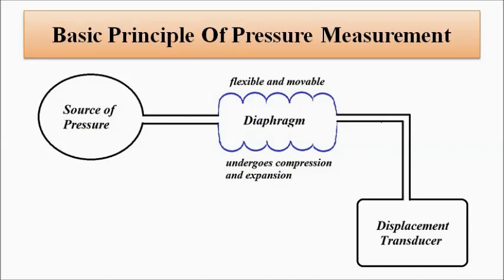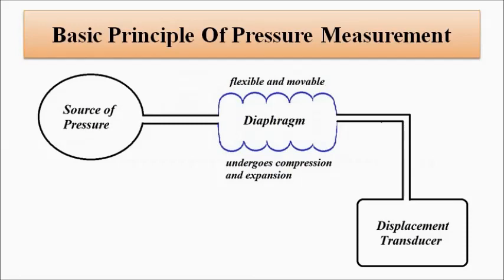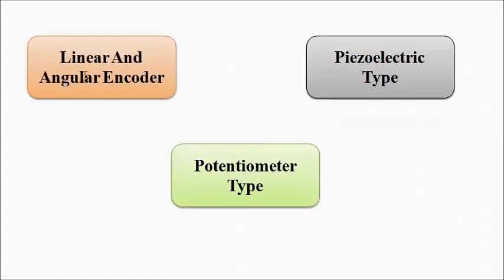For the principle of measurement of pressure, two sensing elements are required. A primary sensing element called the diaphragm is connected to the source of pressure or the body part. It detects the pressure fluctuations, causing it to expand or get compressed. That compression and expansion is detected by a secondary sensing element — the displacement transducer — which gives an electrical output. Different types of displacement transducer can be used: capacitive, inductive, strain gauge, differential transformer (LVDT), linear and angular encoders (optical and magnetic), piezoelectric, or potentiometer type.